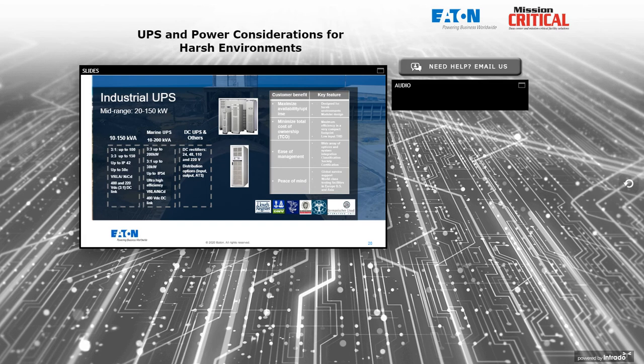So let's take a look at a little bit larger industrial UPSs here, what we'll call the mid-range, say from 20 to 150 kW. These are typically 3-phase input, and most of them are 3-phase output. We do see in the 10 to 30 kilowatt range a surprising number of industrial clients where they're feeding a single-phase panel on the output of the UPS, and they're requesting a 3-phase input and a single-phase only output. Now, that's absolutely fine from a functional standpoint. The UPS can be designed to do that.